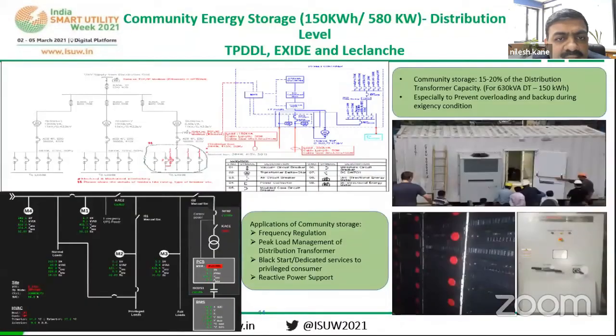This is the community energy storage I mentioned. We have interconnected it on the substation transformer, with two buses, a preferred bus and a main bus, to take care of important loads. In the event of transformer failure or power supply failure, it is interconnected on the LT side, so important customers like hospitals will be taken care of using the smaller distribution transformer. We considered 150 kilowatt for 4 hours, since within 4 hours we are generally able to restore power supply in the utility. We are successfully using this in a congested area of Rani Bagh in Pitampura in Delhi.